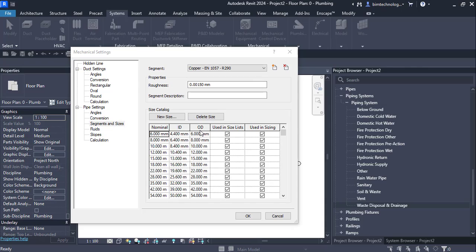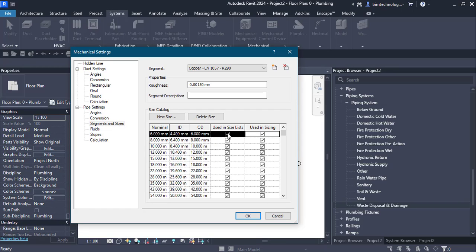Under segments and sizes you have different segments with a size catalog listed. There is a column for nominal diameter, internal diameter, outer diameter, and then checkboxes for using the size list and using sizing. For example, at a nominal diameter of 6mm, the internal diameter is 4.4mm and the outer diameter is 6mm. If the checkbox is selected, this size will be used during pipe sizing and when selecting sizes from the drop-down.